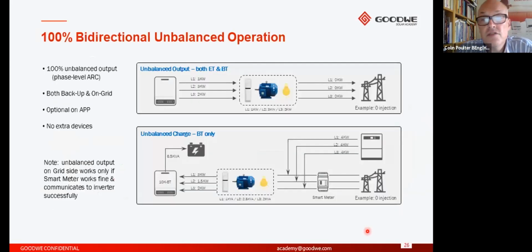Okay, so I said I'd return to talk about the bidirectional unbalanced output capability. I've just got a couple of little diagrams here to help explain this. At the top here, for both the ET and the BT, we have the inverter, and we're also going to consider the situation where we're not allowed to export anything back to the grid. On phase 1, we have a load of 1 kilowatt. On phase 2, a load of 3 kilowatts. And on phase 3, a load of 2 kilowatts.